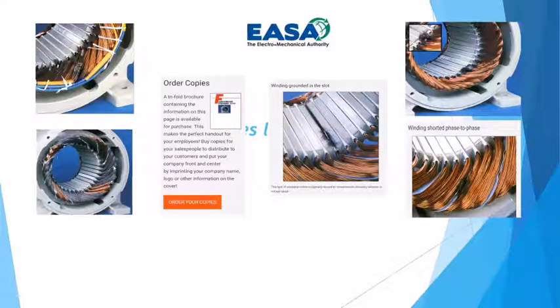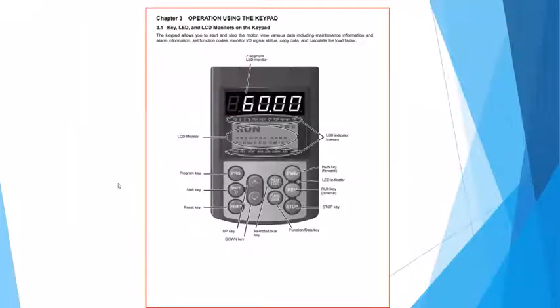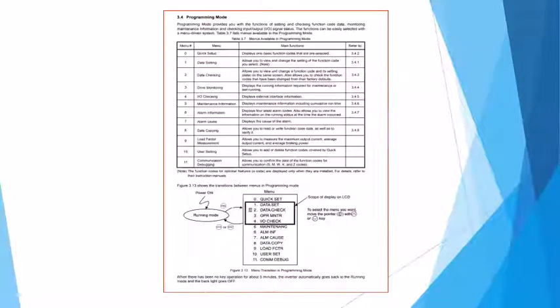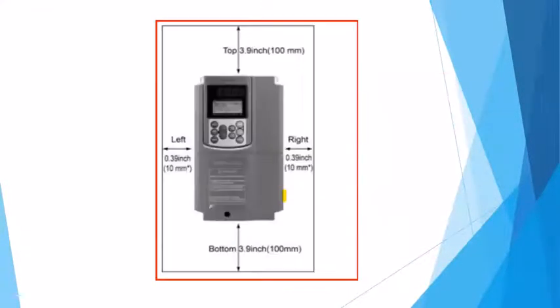It's grown. And then one other thing here is a single phase situation where the load, you can see, went all across 2 phases. One of the phases isn't even burnt, so that shows that one of the power lines got dropped and the motor continued to feed power to it, tried to compensate and keep it running, but over time it smoked the coils out. This is more information about the VFDs.